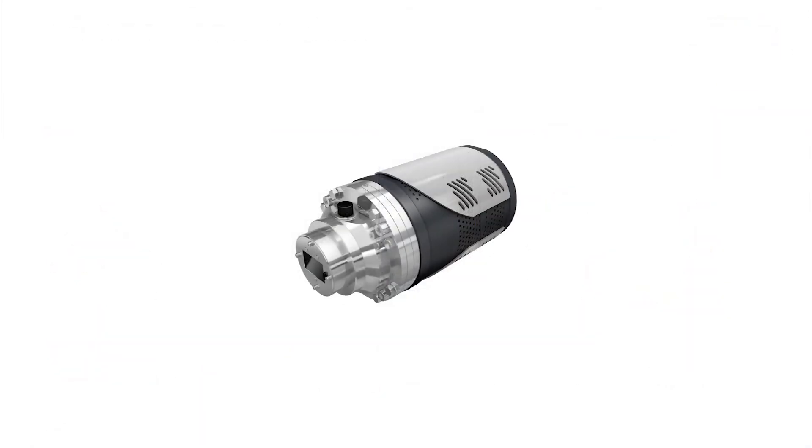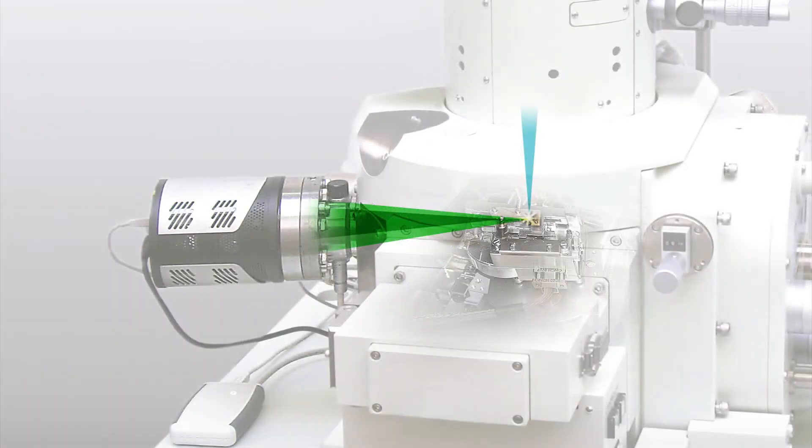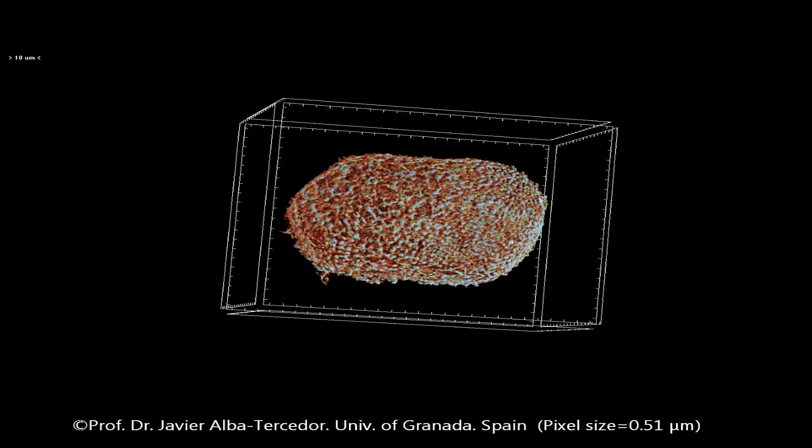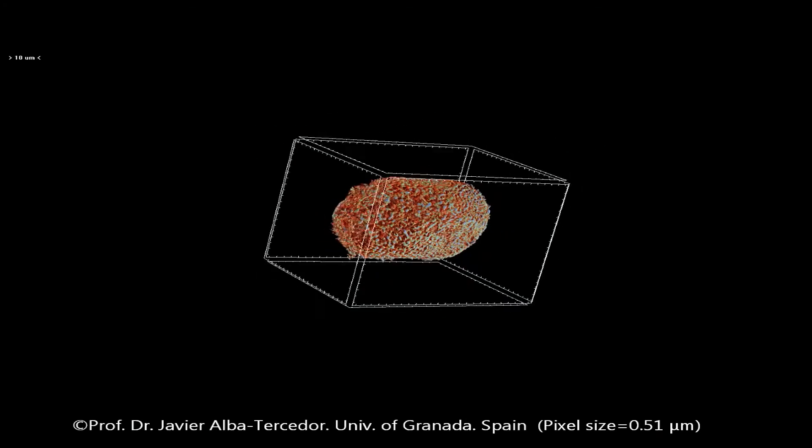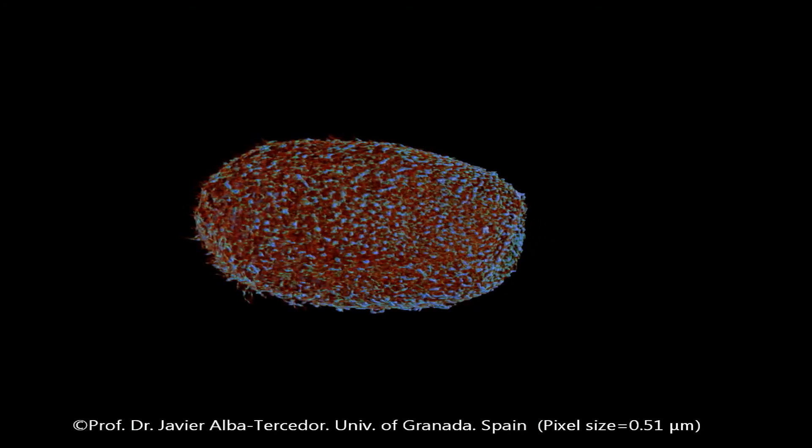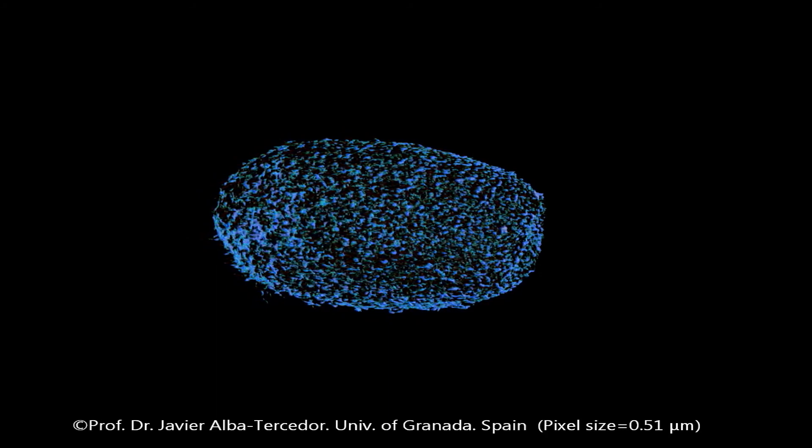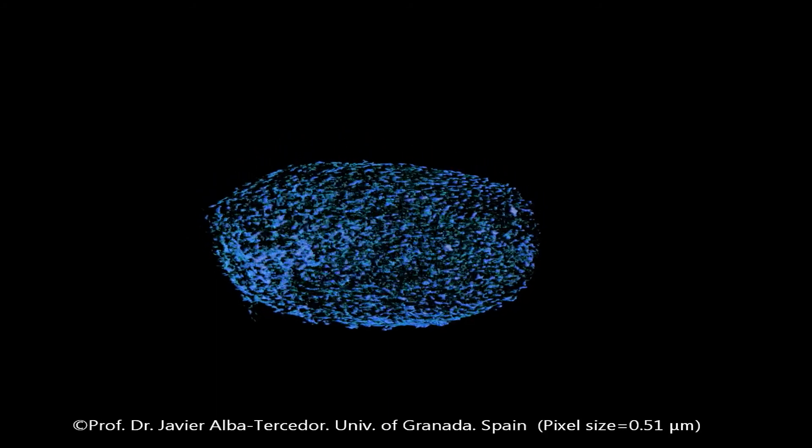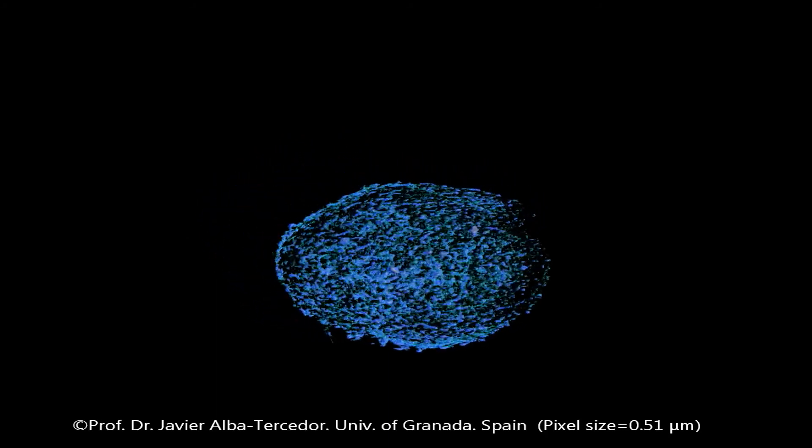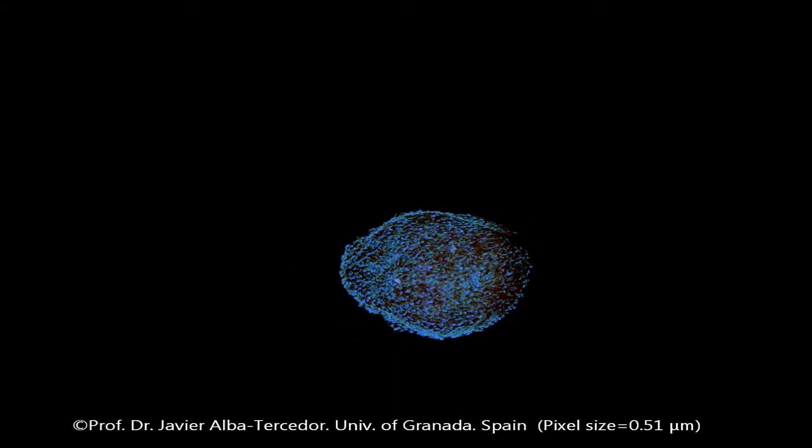To obtain information on a specimen's internal microstructure non-destructively and without any additional sample preparation you can use the microCT for the SEM. The scanning volume of your sample can be 4 mm in diameter with a maximum length of 10 mm. You can detect details down to 400 nm in size.